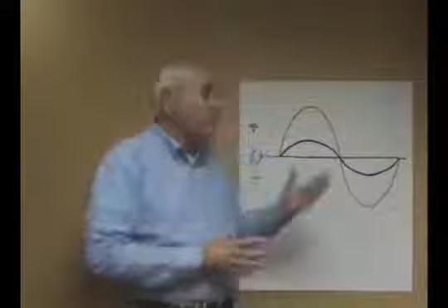But here's the practical side of it. Power quality is the study of the voltage and current sine waves we apply to our equipment, and that certainly applies to the premises distribution wiring system in our buildings as well. If the equipment operates properly and the wiring system functions properly, we might say we've got good power quality. But if the equipment runs into problems, or if we have wiring system issues such as neutrals overheating or transformers burning up, then we might say we have poor power quality.